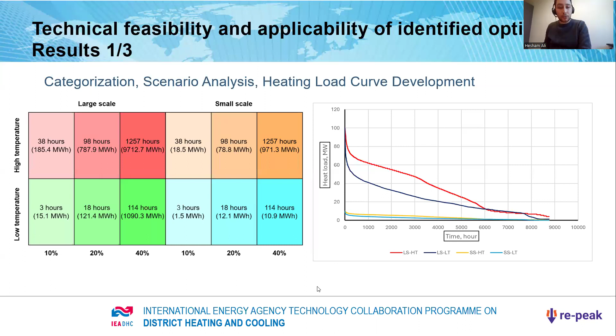And when the peak load capacity covers 40% of the total capacity, the occurrence of the peak load in the high temperature network will be over 1,200 hours, while in the low temperature district heating network it will be around 100 hours per year. And now we have the hours where the peak load units can be operated and the amount of thermal energy to be output from the peak load units in the different scenarios we have.